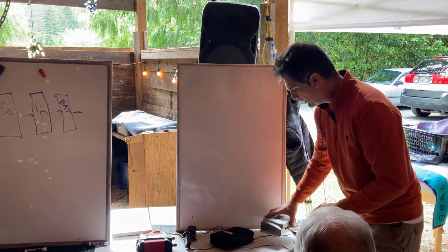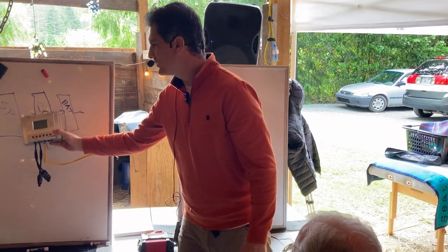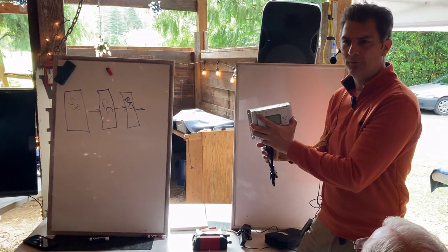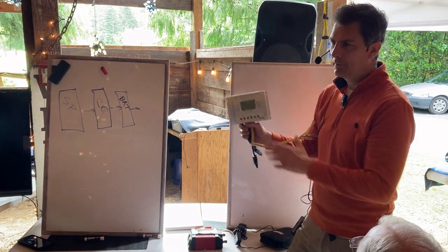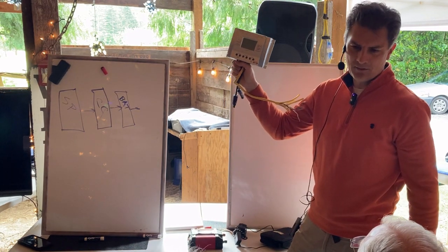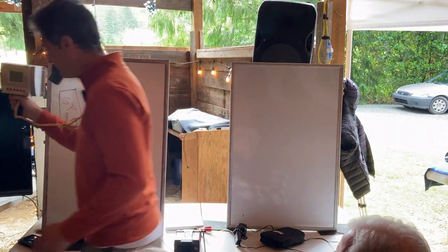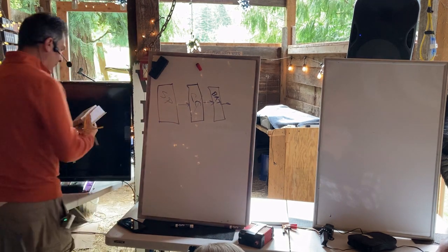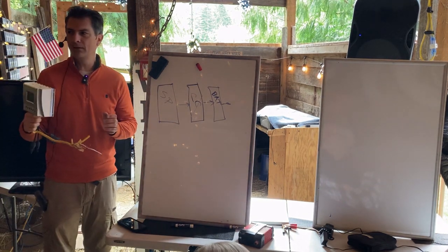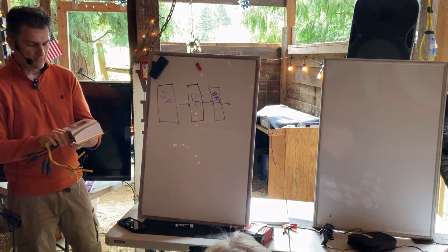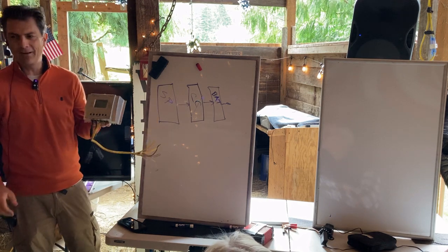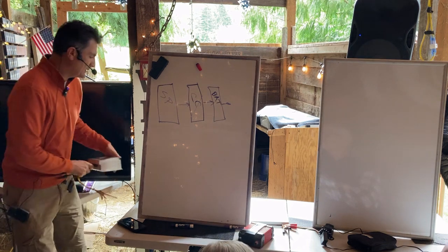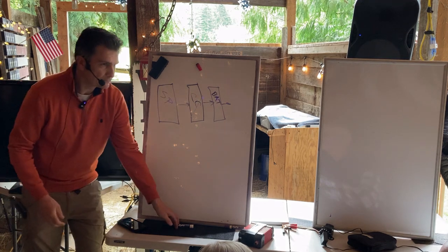But this charge controller in between, you're going to find cheap charge controllers like this online. And you want an MPPT if you want an efficient charge controller. But let me tell you, if you are getting this one, it is not an MPPT like it says. It's actually PWM. Oopsie. Just because something says it's something doesn't mean it is. Anyway, I love them. They're 60 amps, but unfortunately they're not MPPT controllers. MPPT stands for Maximum Power Point Tracking.